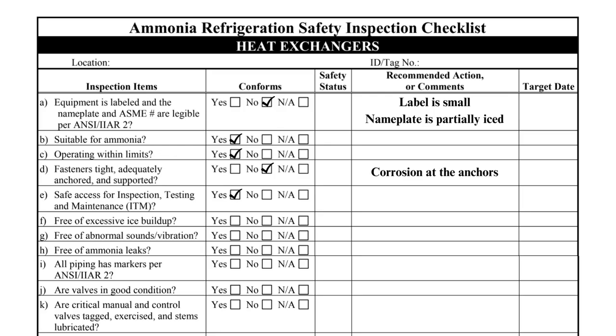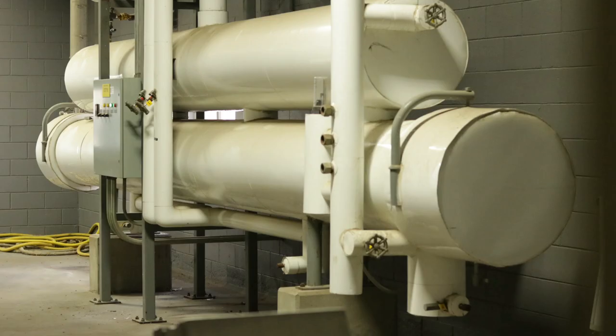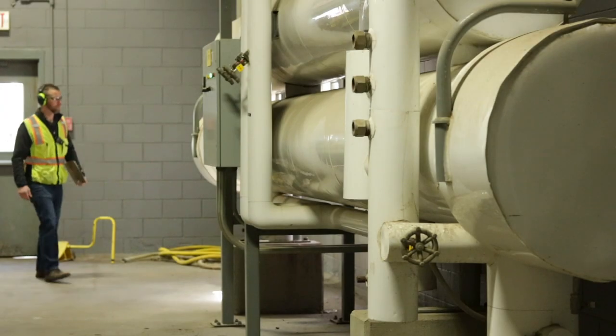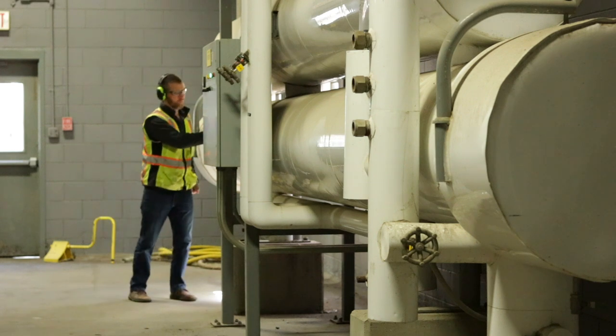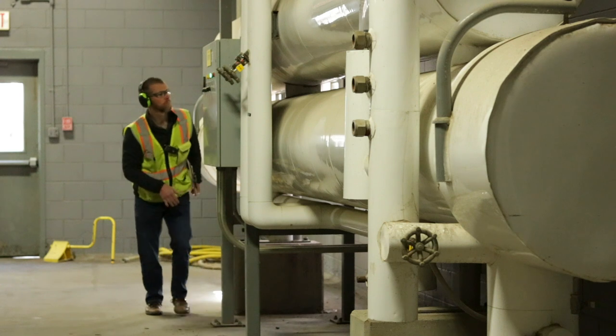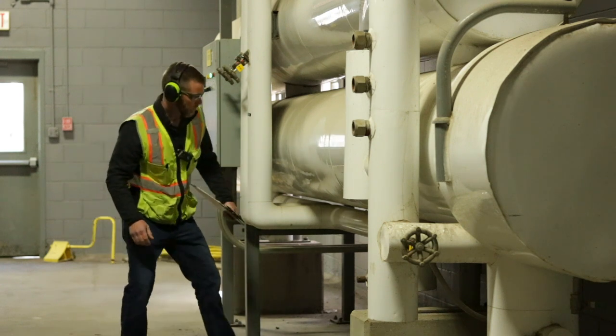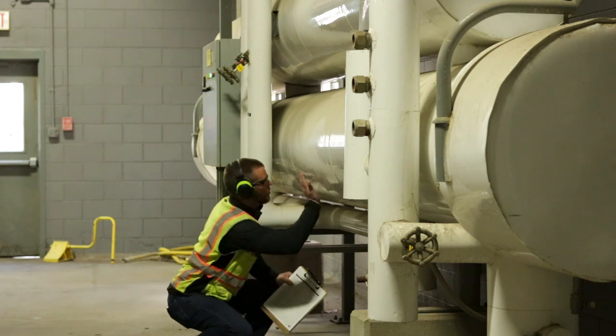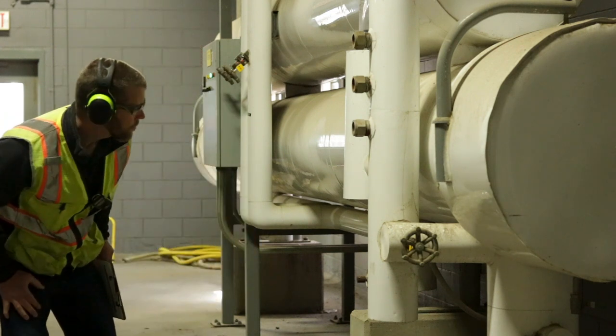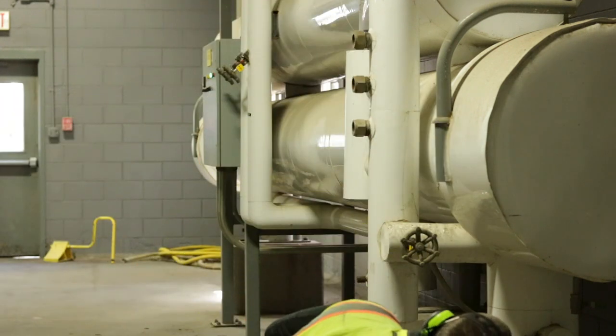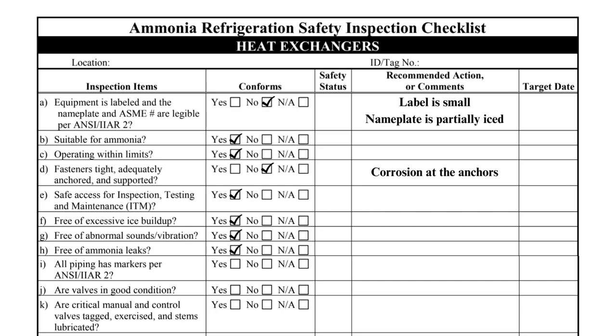The heat exchanger should have safe access for normal service and maintenance. This heat exchanger is mounted to the ground, so safe access is acceptable for inspections, testing, and maintenance. The inspector must do a visual inspection of the entire heat exchanger to verify the equipment is free from excessive ice buildup, vibration, and leaks. Where possible, the heat exchanger should be inspected from all sides to avoid missing a deficiency. Item F asks specifically about ice buildup. Since the heat exchanger is on the low side of the system, it is common to see some ice buildup when the system is in operation, but excessive ice must be recorded and addressed.